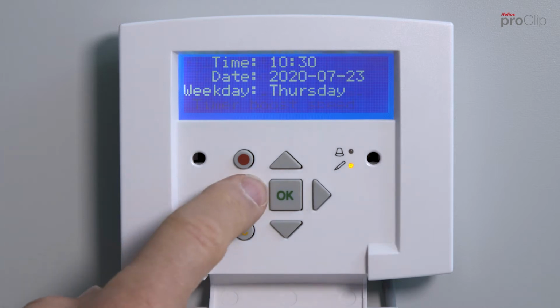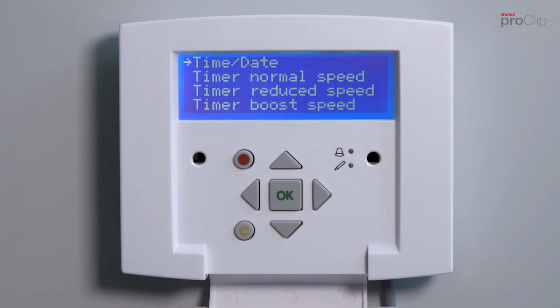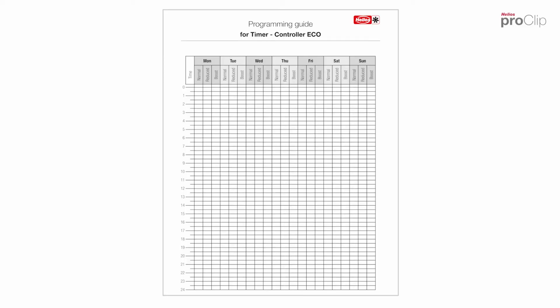We will show you how to program the timer using an example. We will program the following switching times for Monday. The unit will be operated at the normal operating level from 7 to 18 hours. The ventilation unit will run at the reduced operating level from 0 to 7 hours and 18 to 24 hours.